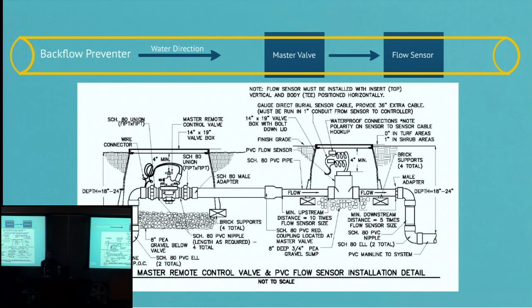The way to get familiar with what sizes look like is just have the manufacturer come in and give you a demonstration on their master valve and what size looks like what size. The next thing after that would be your flow sensor. And the flow sensor, you can see right here there's a section of pipe and another section of pipe. The flow sensor needs to be installed with these certain lengths of pipe between the master valve and the flow, or actually between this fitting and the flow sensor, and this length of pipe and this fitting.